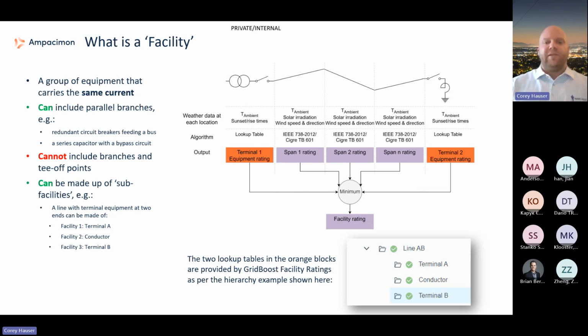Equipment often has fixed ratings, but there are standards in place that allow us to ambient-adjust it. The ultimate output of this is determining the most limiting piece of equipment, second most limiting piece of equipment, in the entire facility as a whole—looking at terminal equipment, the conductor, everything, and factoring it all in to find that most limiting piece of equipment.